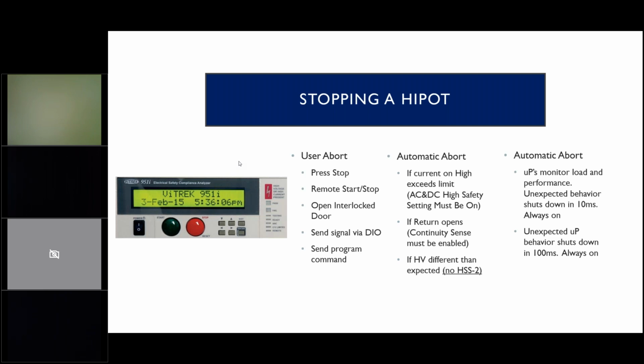So how do you stop a HIPOT? Well, this is part of a front panel of one of ours, and you have about 5 different ways you can stop it. One of which is to press stop, that big red button, pretty easy to do. You also have a remote start-stop switch you may have enabled, and you can just hit that button. You can have an enclosure, and that enclosure can be interlocked, so you basically just open the enclosure and it will shut off automatically. You can send a signal electronically via our digital input-output jack, and you can send a program command via things like Ethernet. So lots of different ways to stop it, but it will do it automatically too. It's watching itself, and it's pretty smart.